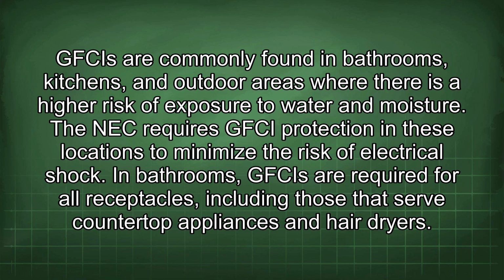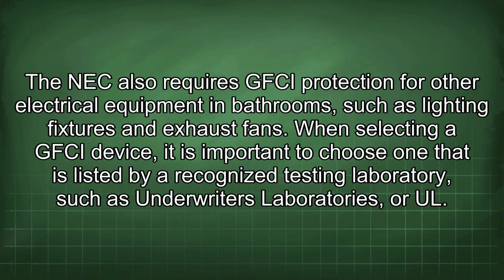GFCIs are commonly found in bathrooms, kitchens, and outdoor areas where there is a higher risk of exposure to water and moisture. The NEC requires GFCI protection in these locations to minimize the risk of electrical shock. In bathrooms, GFCIs are required for all receptacles, including those that serve countertop appliances and hair dryers. The NEC also requires GFCI protection for other electrical equipment in bathrooms, such as lighting fixtures and exhaust fans.